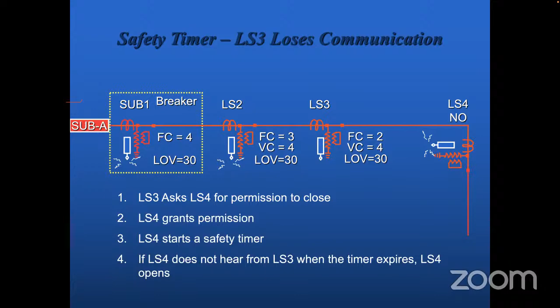Very practical - there's a safety timer. Circuits are looped together again. LS3 asks LS4 for permission to close. LS4 grants permission, and LS4 starts a safety timer. This is what I was mentioning about communication - you have to program it so that if you don't get a response, something happens. So if LS4 does not hear from LS3 when the timer expires, LS4 opens up.